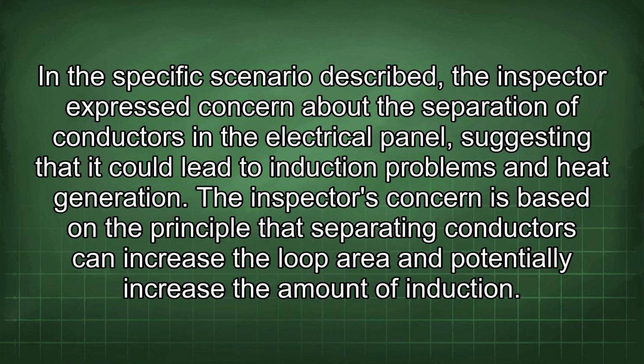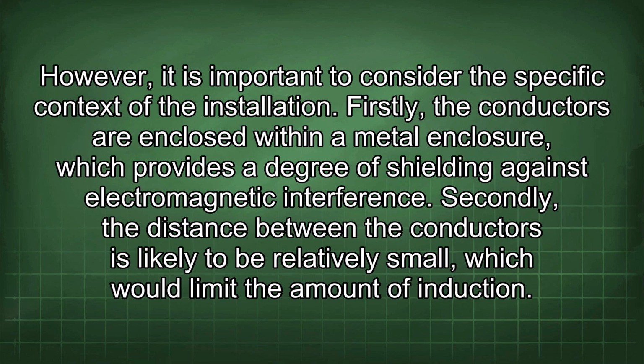In this specific scenario described, the inspector expressed concern about the separation of conductors in the electrical panel, suggesting that it could lead to induction problems and heat generation. The inspector's concern is based on the principle that separating conductors can increase the loop area and potentially increase the amount of induction. However, it is important to consider the specific context of the installation.